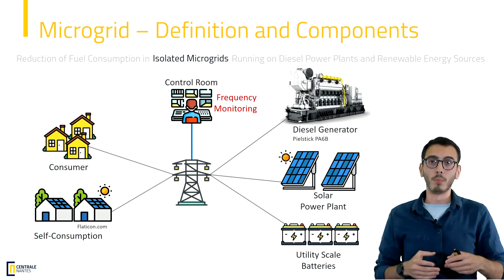Right now, if you check any plug in France, the frequency will be 50 Hertz. If for any reason it's at 49 Hertz instead of 50, it means there's a problem on the grid, and the controller inside the control room will know there's a deficit between power demand and power produced, and will apply changes to bring back the balance.